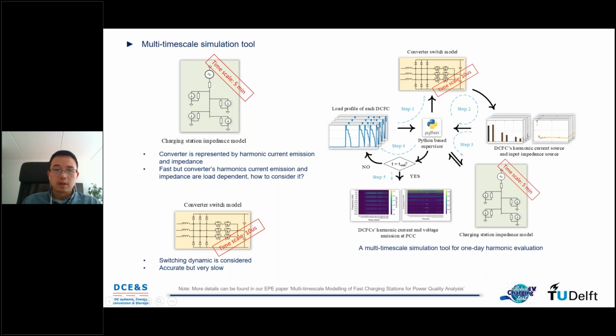First, you start from the load profile or charging profile of the charger. Each time you take one operation point. Then you go to the converter switch model and make sure the converter is operating at that specific operation point. Then you extract the current source and impedance of the charger, and input this time variant impedance and current source into the impedance model of the charging station. Then you'll be able to evaluate the harmonics in a short period of time.